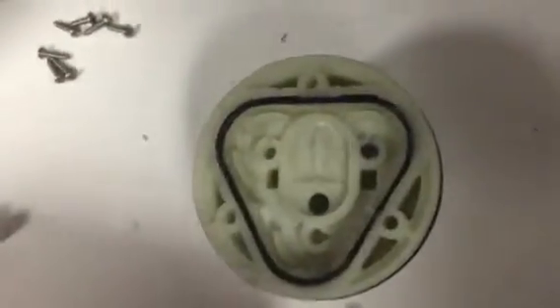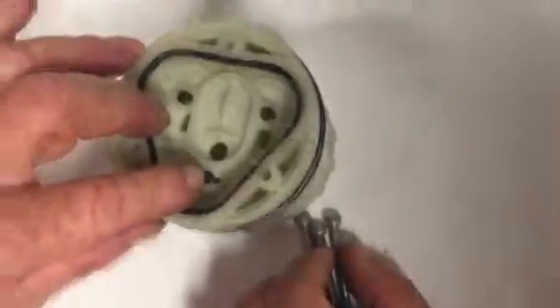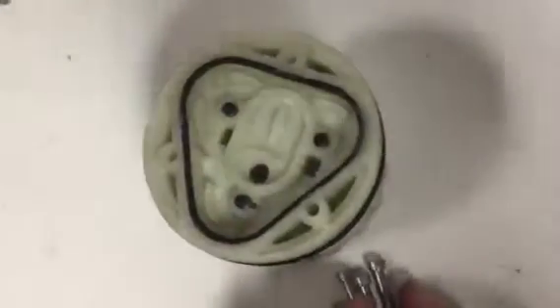That's in place. Proceeding with the pump head, first thing we'll do is we'll take the internal bypass springs and poppets, and as you place them into their holes, there is a locking mechanism at the bottom. When you push them in firmly, they will snap into place, as shown. They can be placed in any order. All 3 of them are the same. Okay, now the internal bypasses are in place.